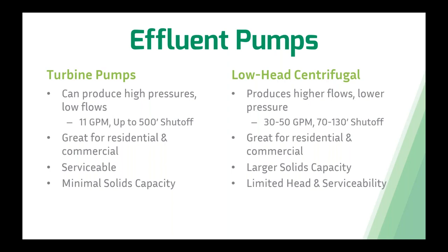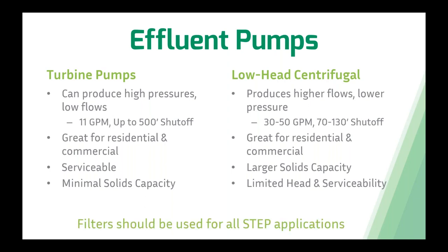The low head centrifugal is what you would typically imagine as a submersible effluent pump. These produce higher flows but lower pressures — average flow of 30 to 50 gallons per minute with shutoff heads of 70 to 130 feet. They meet larger solids capacity requirements, which is an advantage in jurisdictions requiring a minimum half-inch solid passage. The drawback is limited head and lower serviceability — failures generally mean replacing the whole pump. Regardless of pump type, filters should always be used for all STEP applications.